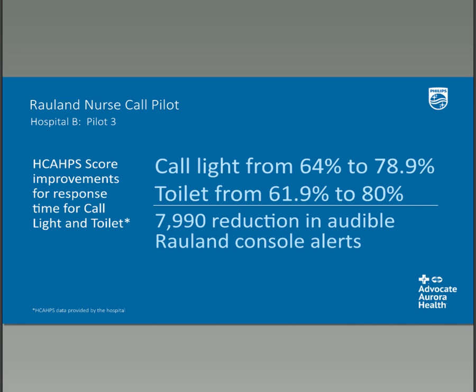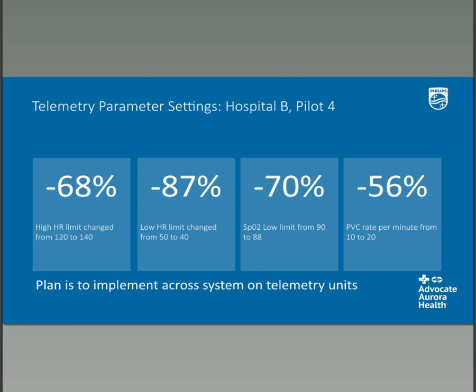Tied to the telemetry performance improvement project, we piloted new default settings for telemetry patients. We changed the high heart rate default from 120 to 140, the low heart rate from 50 to 40, SpO2 down to 88%, and the PVC rate from 10 to 20. Results showed reductions ranging from 56% to 87%. Good results across all the changes.